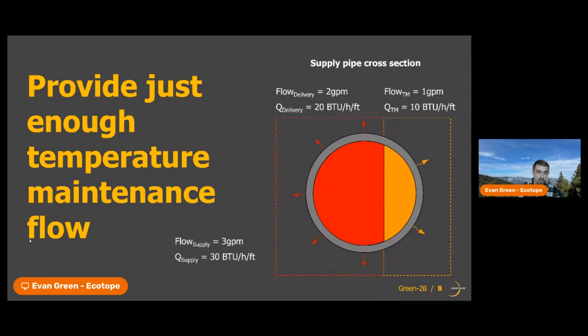If our delivery wanes down a little bit and we only see 2 GPM, now our water isn't flowing quickly enough to get to the tap in time, and it's going to overcool. So we need to provide just enough temperature maintenance flow to be able to increase that flow rate back up to 3 GPM so that water is flowing quickly enough so it doesn't overcool before it reaches that fixture. And since these two flows are mixing together in the same pipe, they're not sitting nicely as I've shown in this pipe here, but they're perfectly mixed together. They're going to be the same temperature throughout that entire pipe.